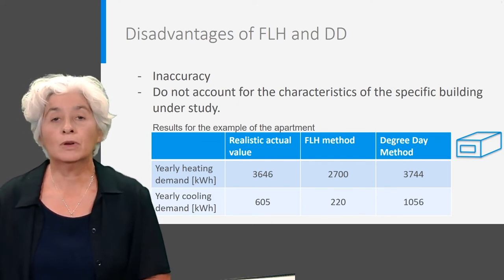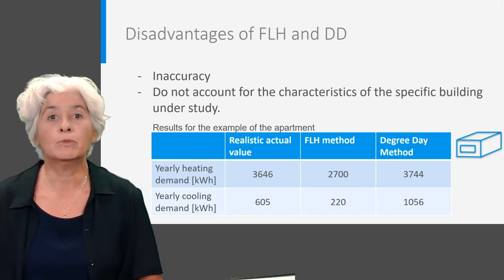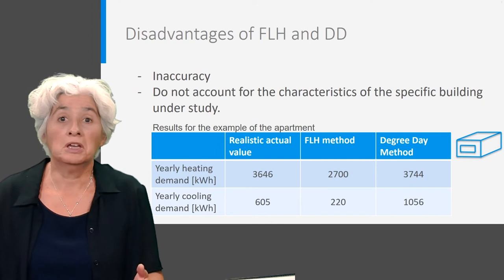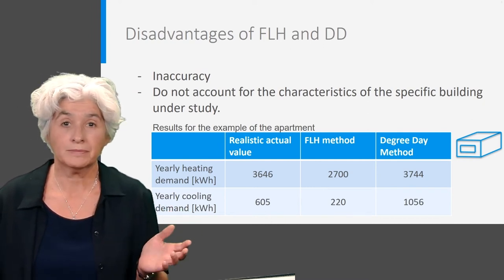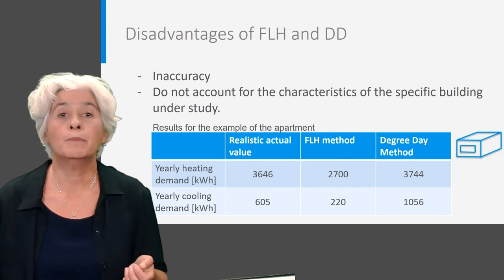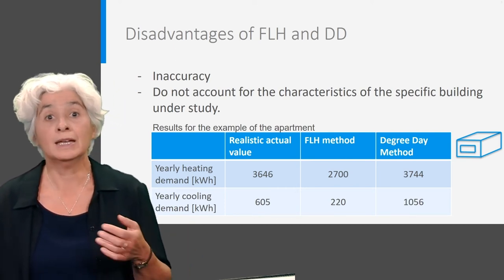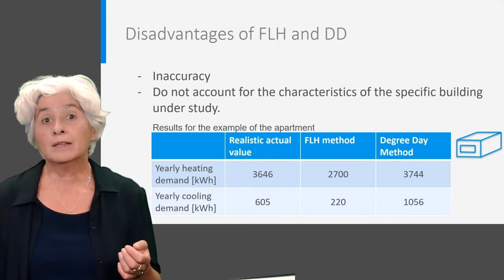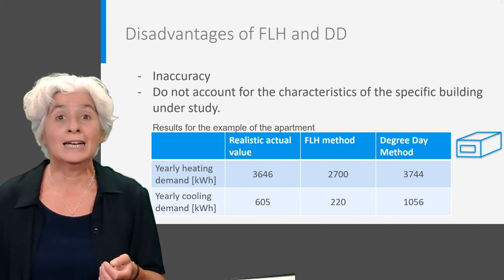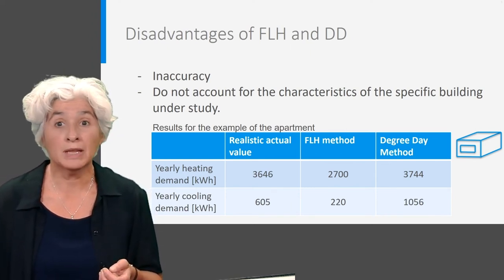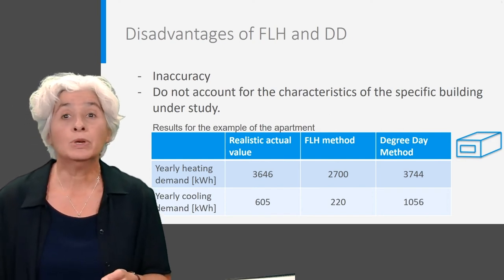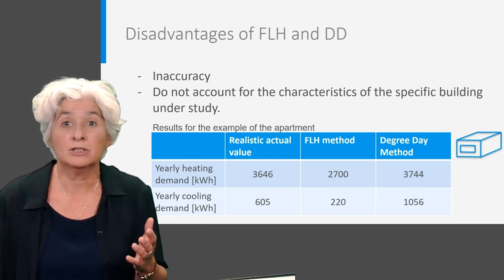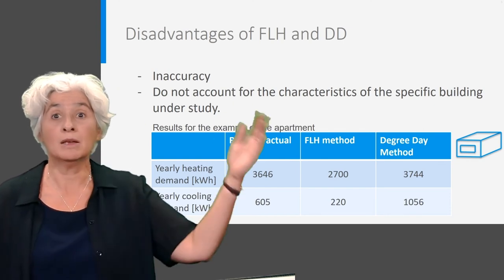In the table, you see the actual realistic energy demand of the apartment building we considered in the example, and the results by the full load hour method and the degree day method. The magnitude is okay, but there are very large errors. It is clear that we need a better method — one that could help us in choosing and sizing the right building components like window size or degree of insulation. These factors are very poorly reflected in full load hours and degree day methods, as their effect is solely accounted for in the determination of the nominal power, which deals with only one short moment in the year. So we know how the window size affects the power at this short moment, but we don't know how it affects it during the remaining part of the year.